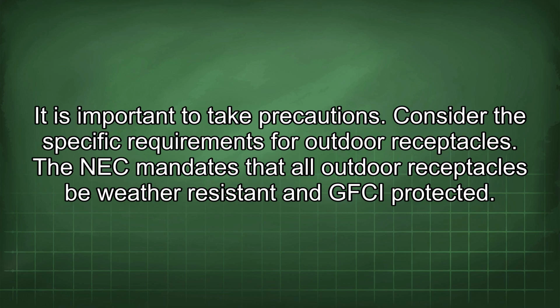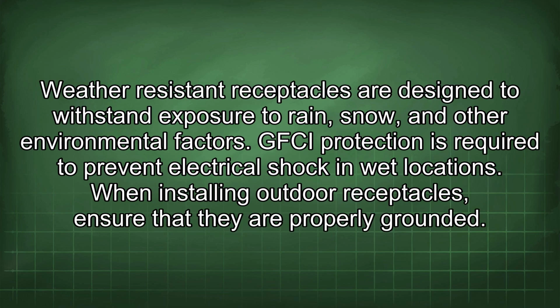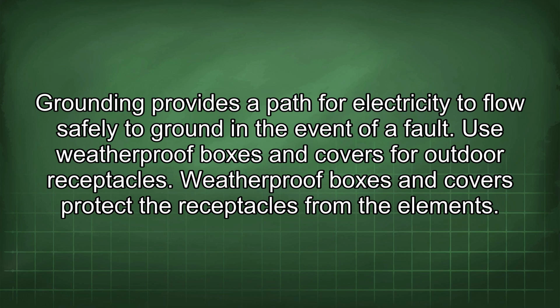Consider the specific requirements for outdoor receptacles. The NEC mandates that all outdoor receptacles be weather-resistant and GFCI protected. Weather-resistant receptacles are designed to withstand exposure to rain, snow, and other environmental factors. GFCI protection is required to prevent electrical shock in wet locations. When installing outdoor receptacles, ensure that they are properly grounded. Grounding provides a path for electricity to flow safely to ground in the event of a fault.